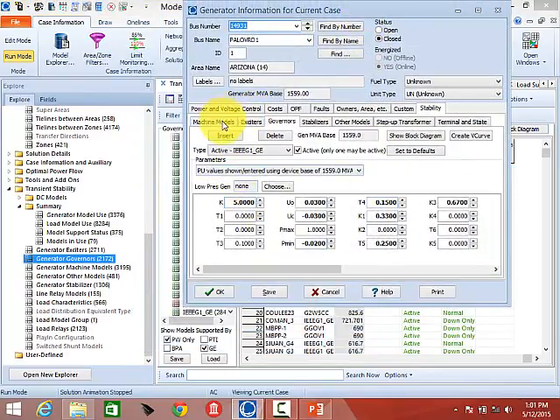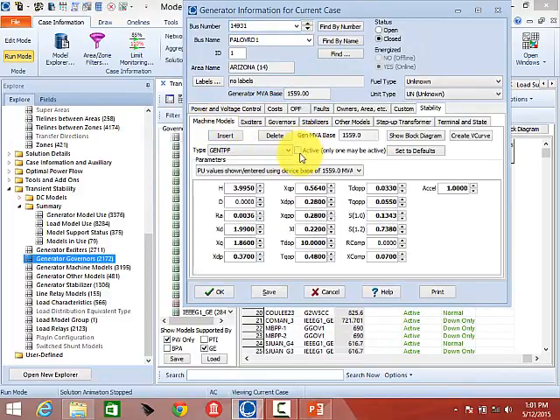When a machine is set inactive it's treated as negative generation — negative load — and there's a flag for how you treat that in terms of voltage dependence, covered in the options. If you disable just the exciter, the stabilizer is also disabled since it feeds into the exciter, but the machine model remains. When you disable the exciter, the field voltage is assumed fixed. Similarly, you can take out just the governor and the machine won't respond to frequency at all — similar to the up-fixed setting but not exactly.